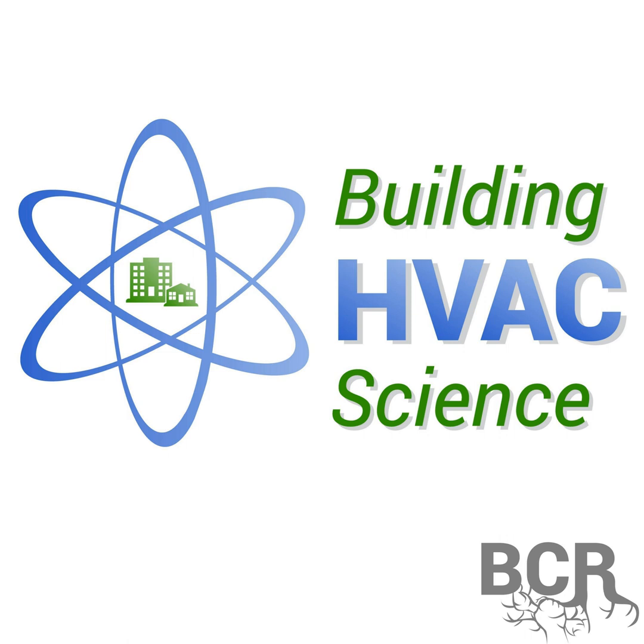In that kind of situation, I guess the first step is we look at the door undercut. In some cases, doors can be really tight to the floor, and we might be able to talk the customer into letting us take a little bit off the underside to provide some pressure relief. And then the next step would be to look at transfer grills, or maybe a jumper duct or something like that. There are transfer grills that can be over the door or through the wall, or even built, cut into the bottom of the door to provide that return air pathway to get back to a central return that's out in the hallway.